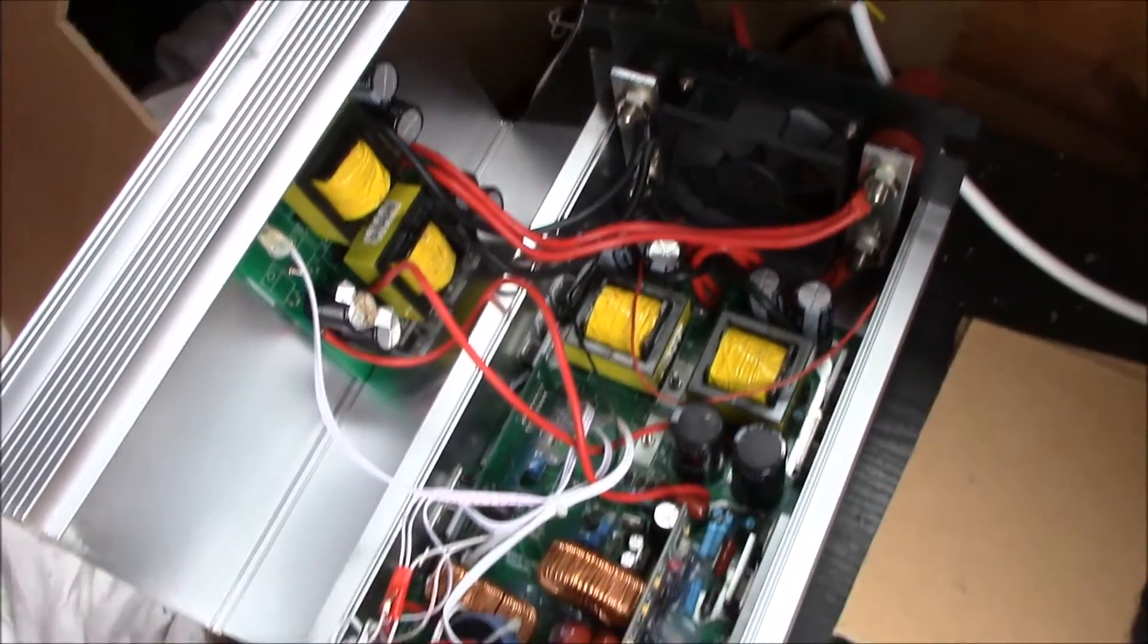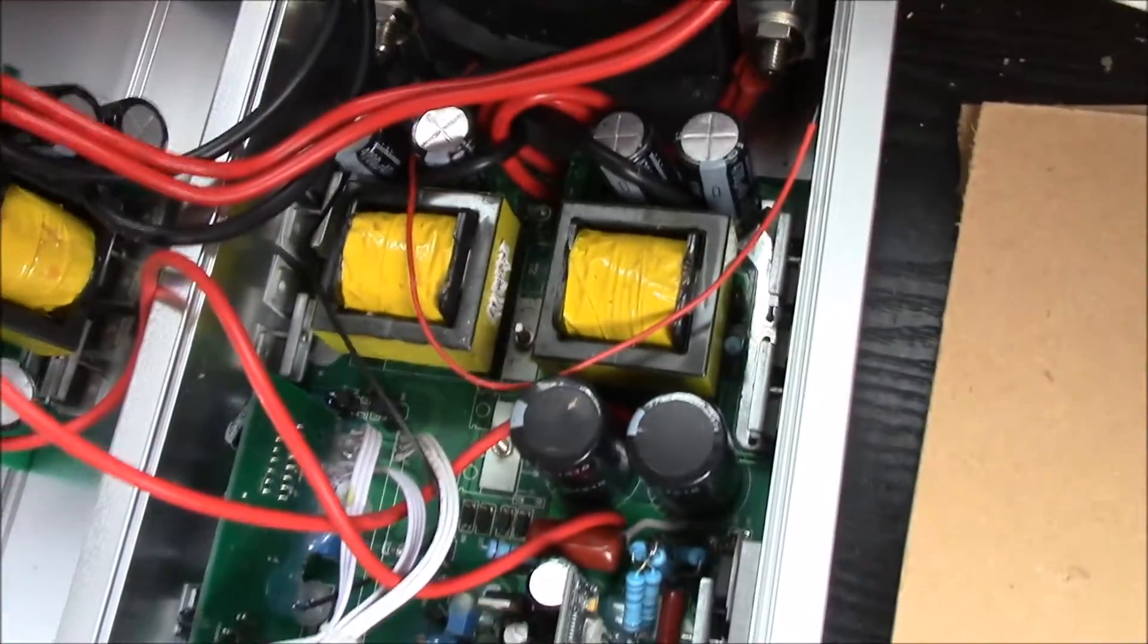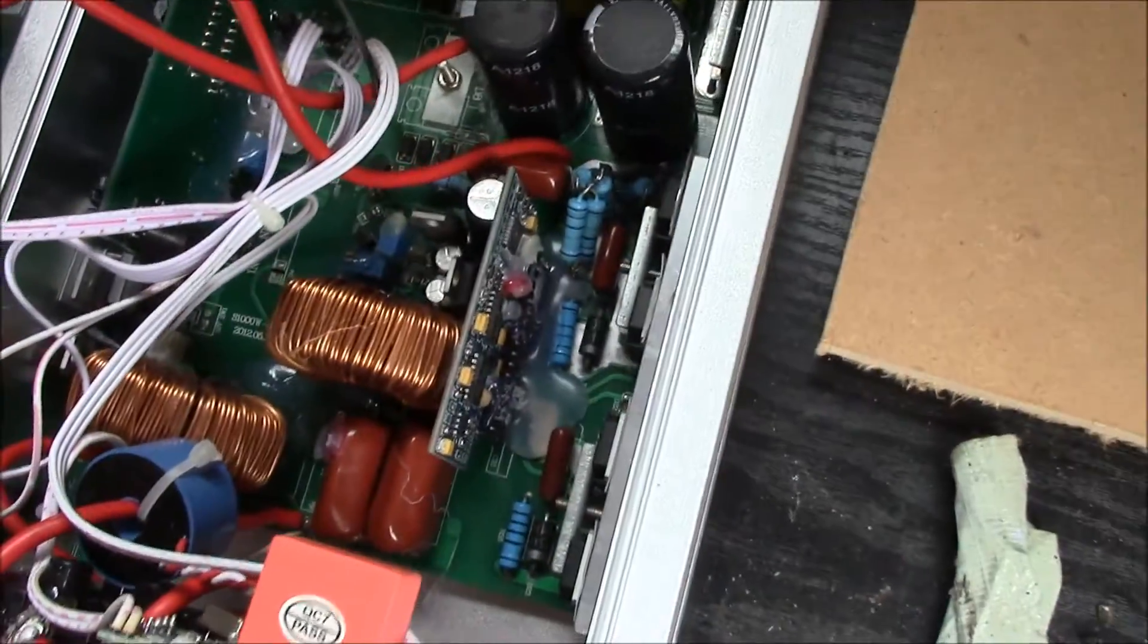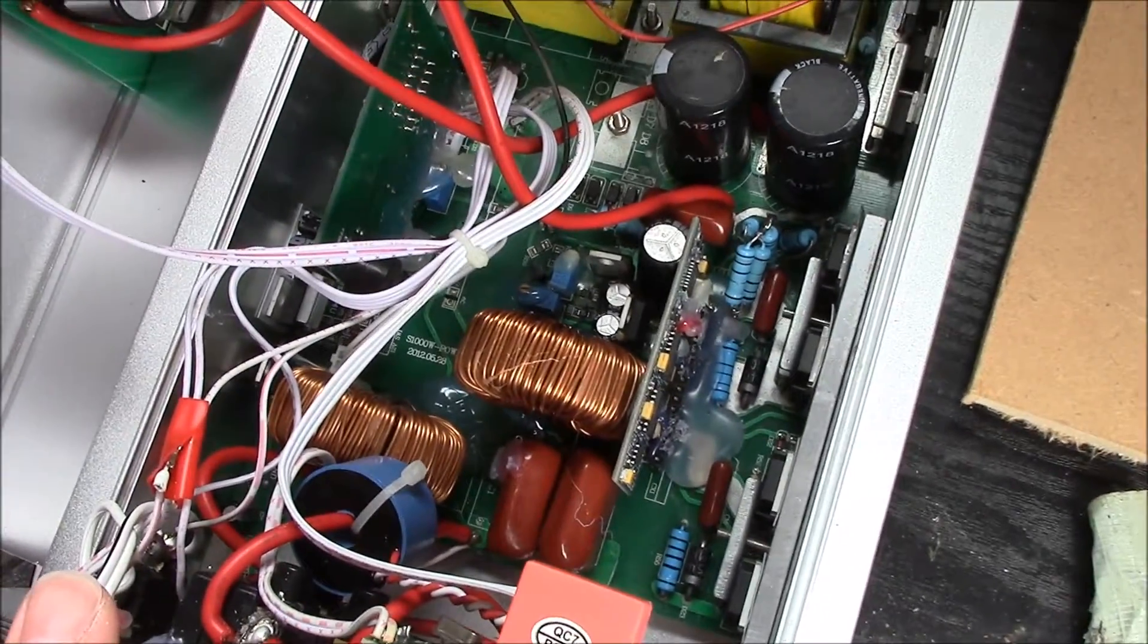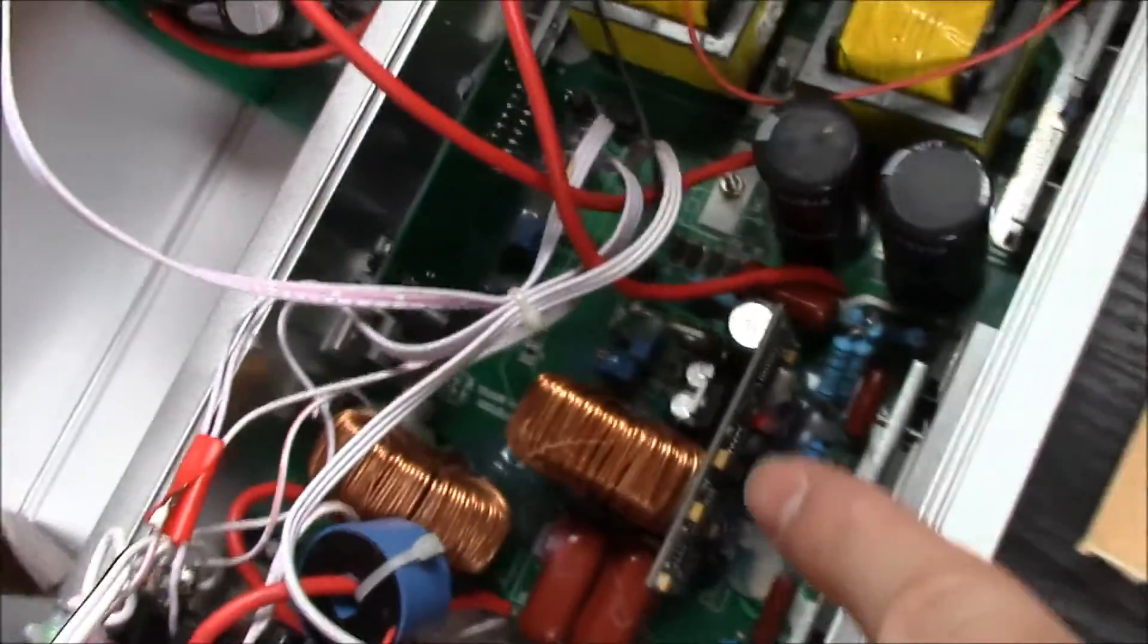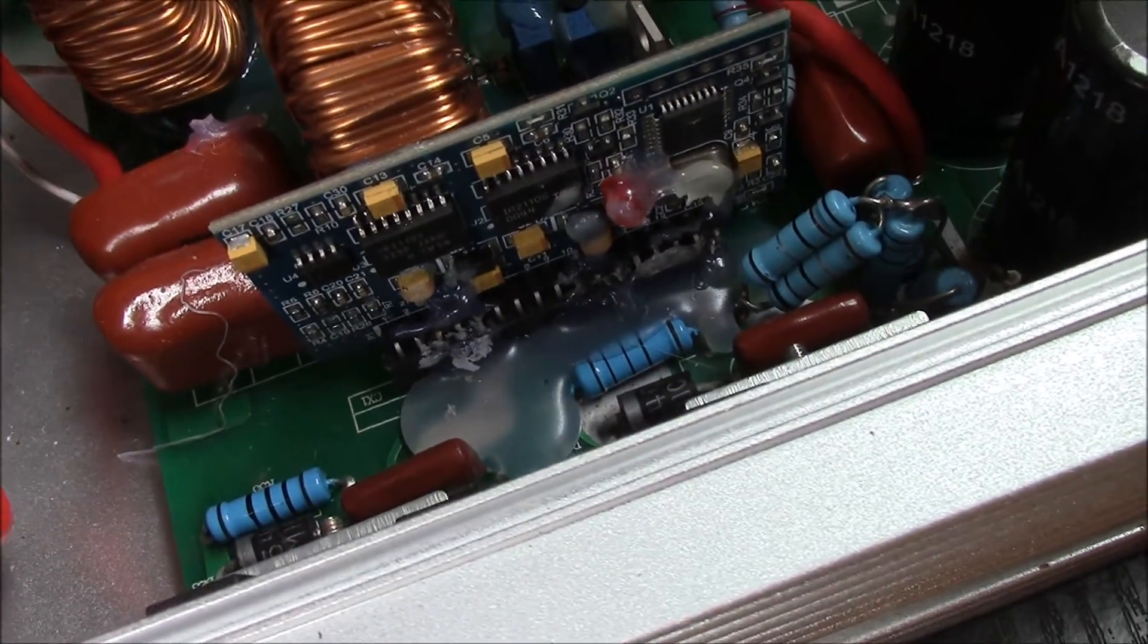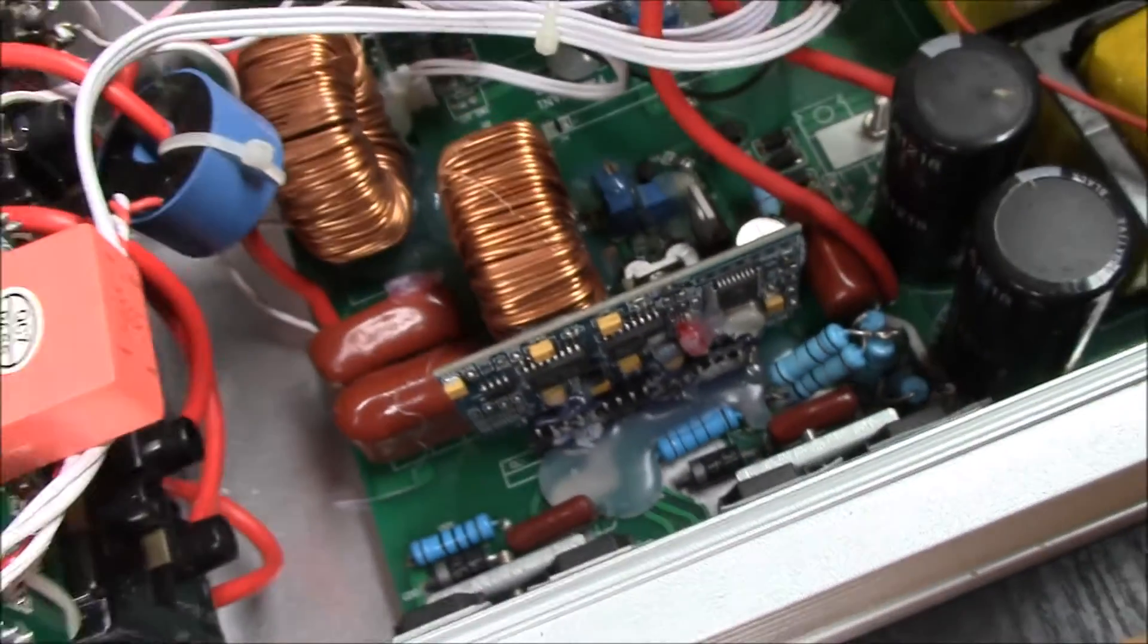So this is with the clamshell open so you can see all the circuit boards. In the back here you've got the high voltage DC to DC converter, so it takes the 24 volts in and converts it up to 300 ish volts, something silly anyway. And then the front end here is your sine wave driver. You've got your BJTs down here which is actually the output. And here is that circuit board that we have online, so hopefully if we pull it out we should be able to adjust it.